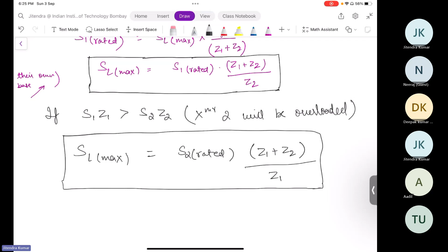In both cases, you will have some SL max. It should be less than S1 rated plus S2 rated. In our question, S1 rated plus S2 rated is higher than SL max, so there is going to be one transformer that will be overloaded. If this condition is satisfied, then one transformer will be overloaded. So the overloading condition will occur.